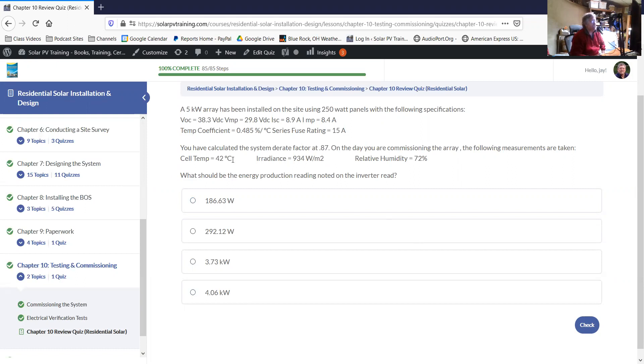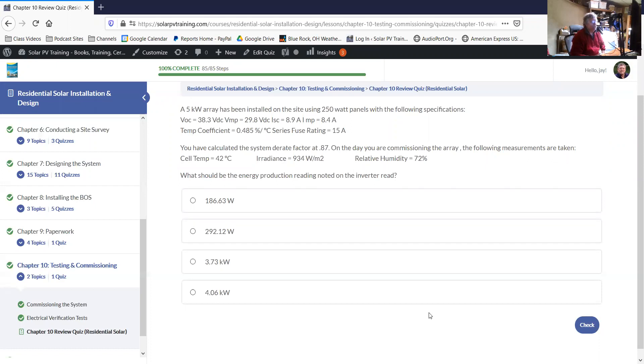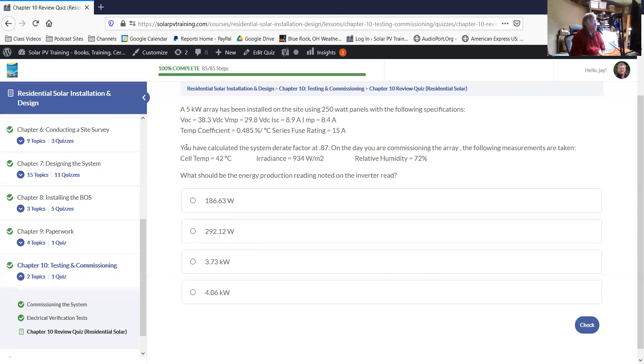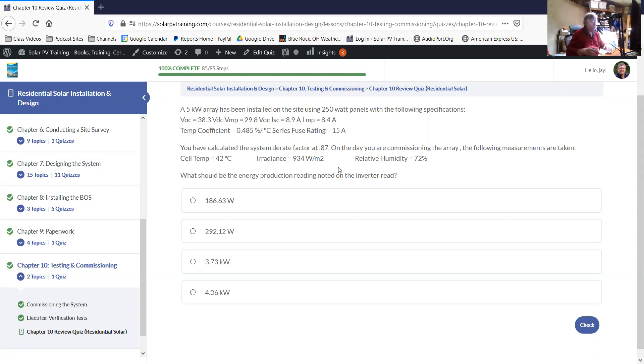Remember, all of our sizing is based on standard test conditions, which are going to be 25 degrees Celsius, and 1000 watts per square meter. And the watts per square meter, the irradiance typically affects amps, and the temperature affects volts. So in this case, we're dealing with a situation where we've measured everything, we're at 42 degrees, that's going to be warmer. So you expect voltage to be less. And irradiance is at 934.